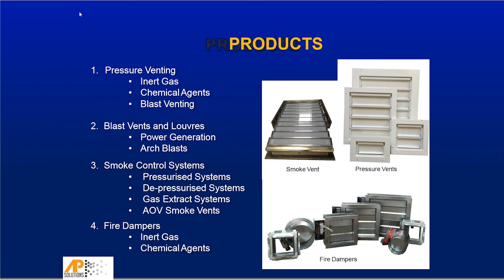And most of the standards suggest that ideally you want to be venting directly to atmosphere, not through sub-areas. But in some cases there is no alternative, and through the testing we did back in 2008, and some subsequent testing on large systems that have failed and we've redesigned and then retested in live discharge testing, cascade scenarios have proved that the theory that we created through our testing actually works in live systems. So it's quite an area that we give a lot of support to our customer base.